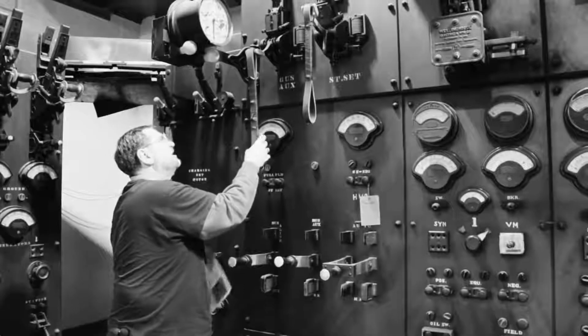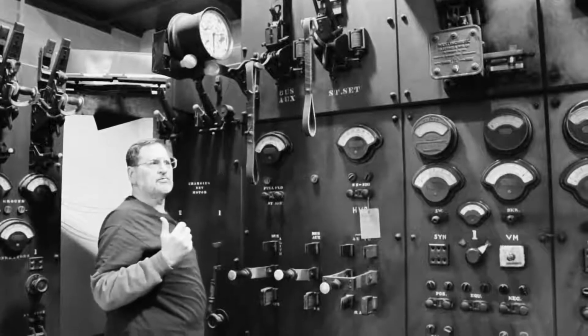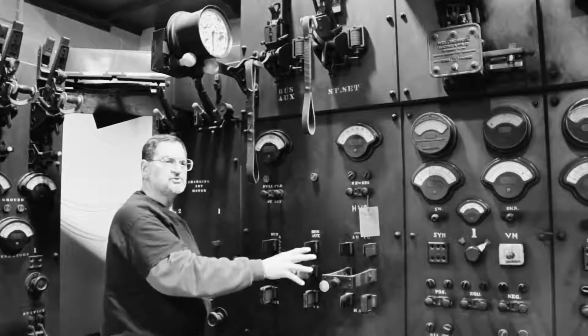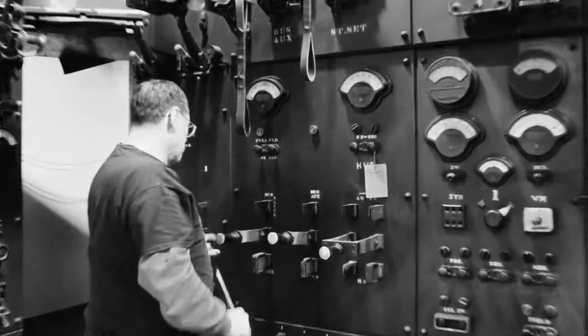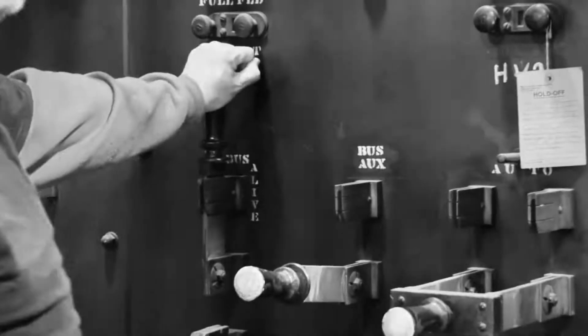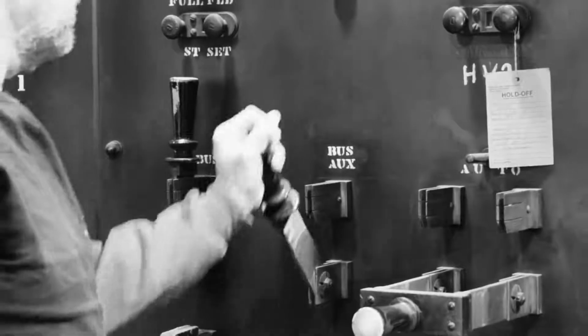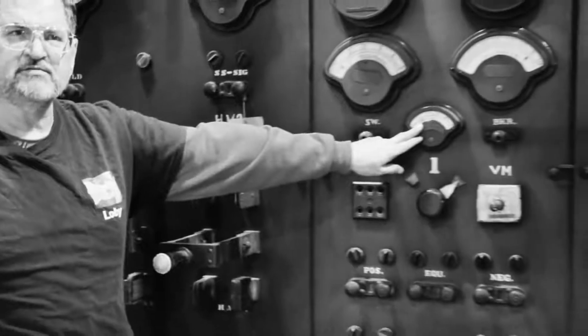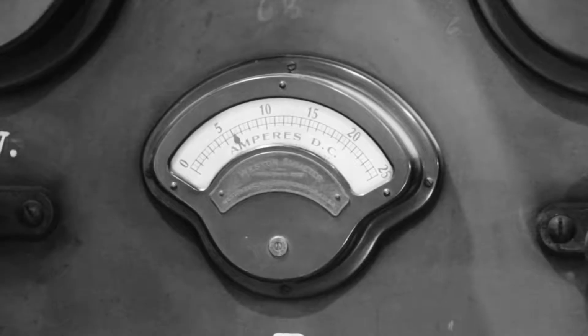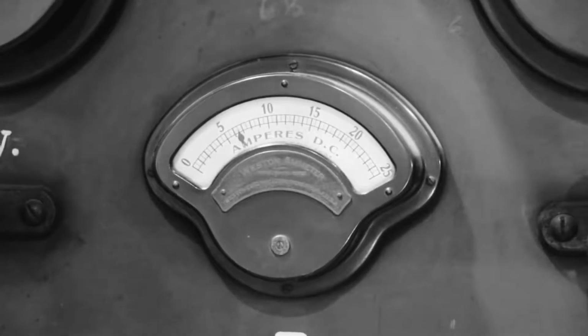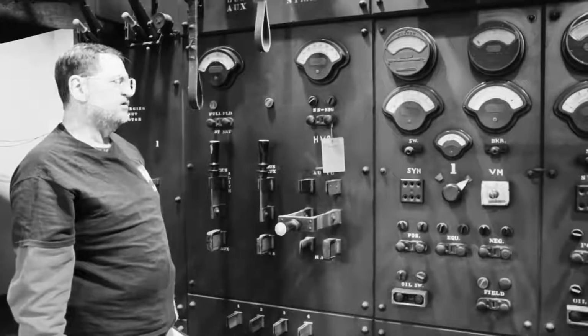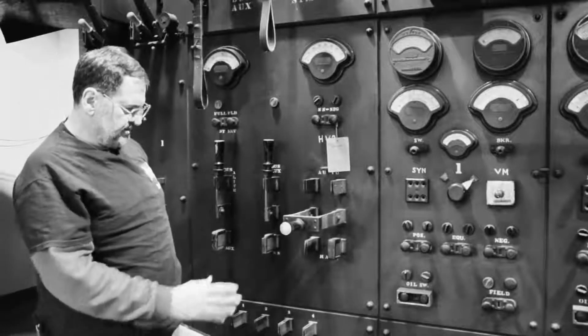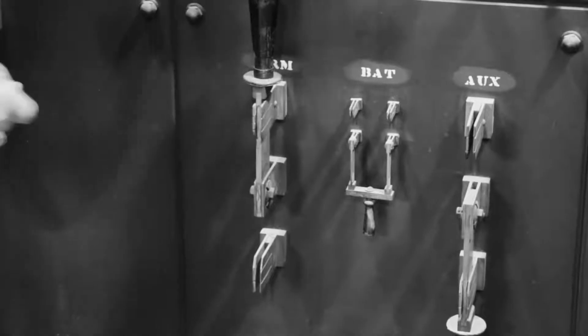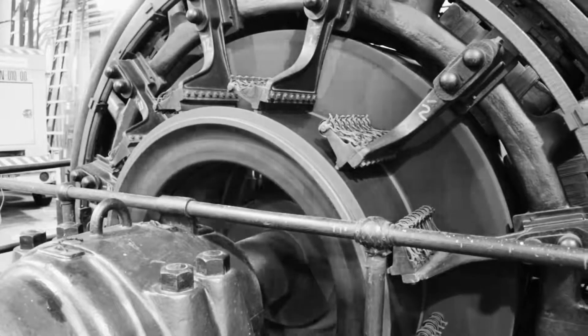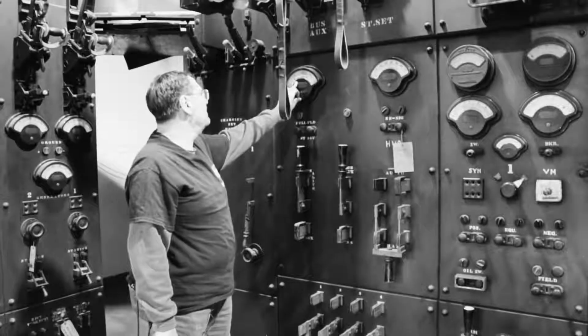And there's the circuit breaker that takes 600 volts from the third rail and makes all the switches alive. Now, one by one, I'm going to slam the bus alive switch in. I'm going to cut in the bus auxiliary. And now the field is alive on the old rotary converter, and it's slowly coming up to its 10 ampere set. And as soon as it hits full field, then I'm going to close the main armature switch, which starts the rotary spinning. Right now the rotary is starting to spin.